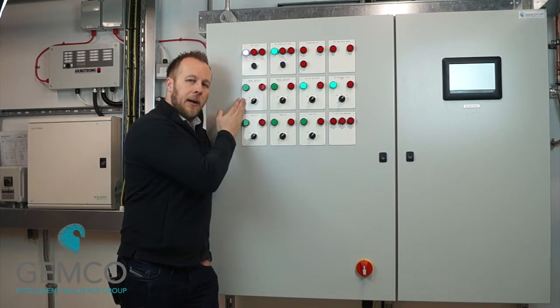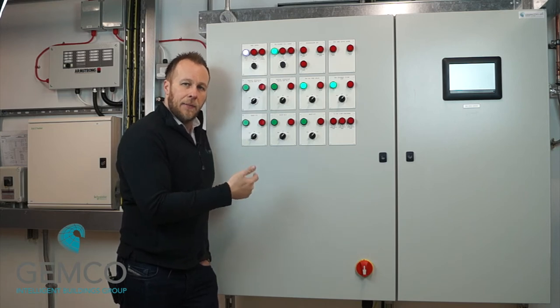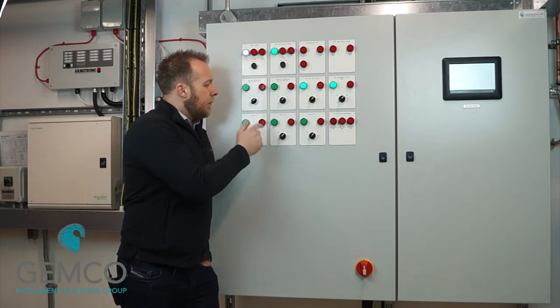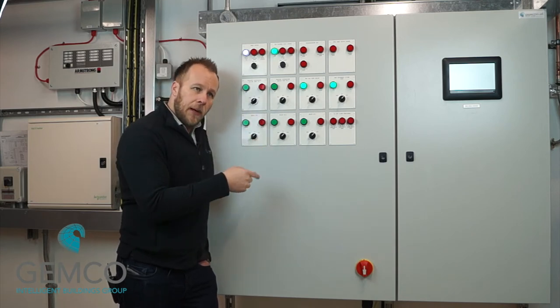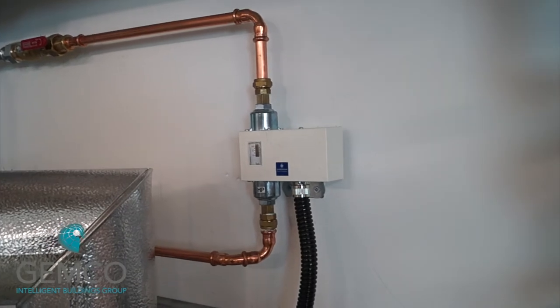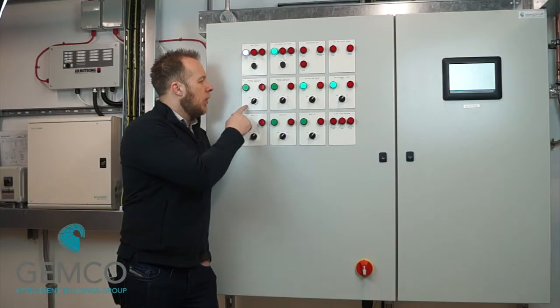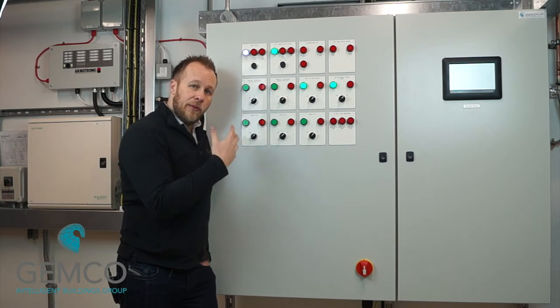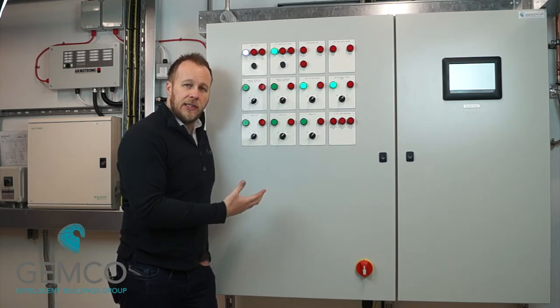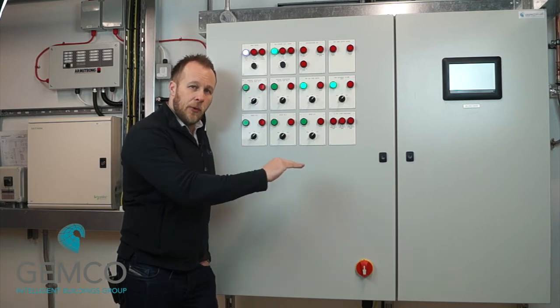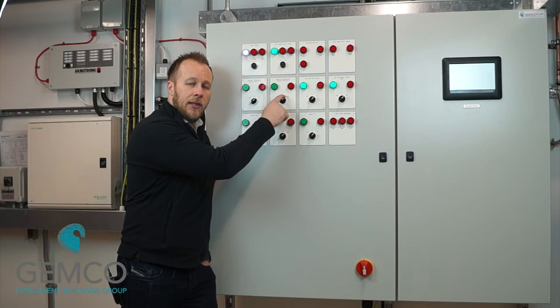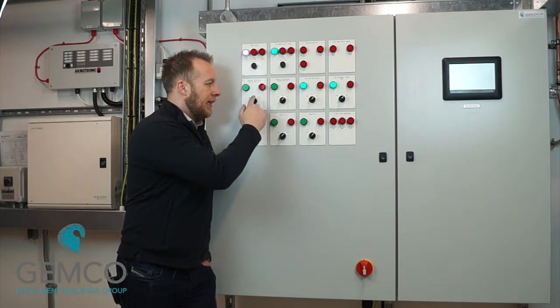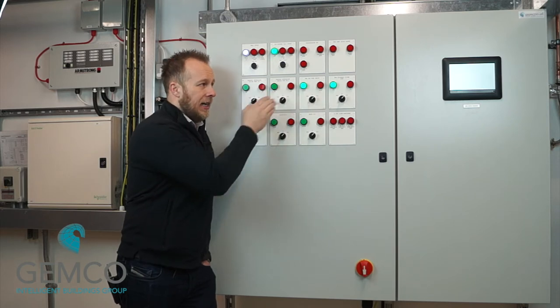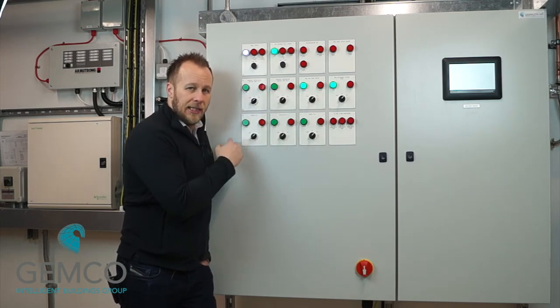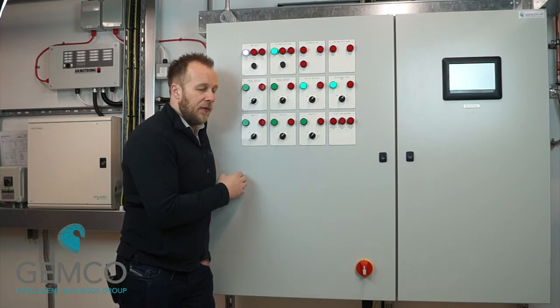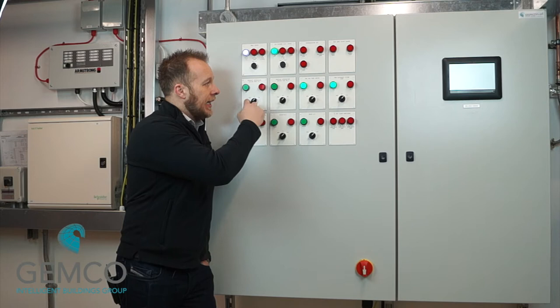But once the duty pump is enabled, once there's a heating demand from either the radiant panels or the air handling units, the control panel will monitor flow across the pump set via that differential pressure switch that's piped up across the pumps. We monitor that for 60 seconds to say, we've enabled the pump, is there flow? And if there isn't flow in 60 seconds, then we cancel the pump, we disable the pump, and we automatically bring on the standby pump. We'll raise an alarm on the pump that had the flow failure, and you'll be able to access the alarms, and you'll need to reset the pump once you've rectified the fault. Okay, but that changes over on a weekly basis.